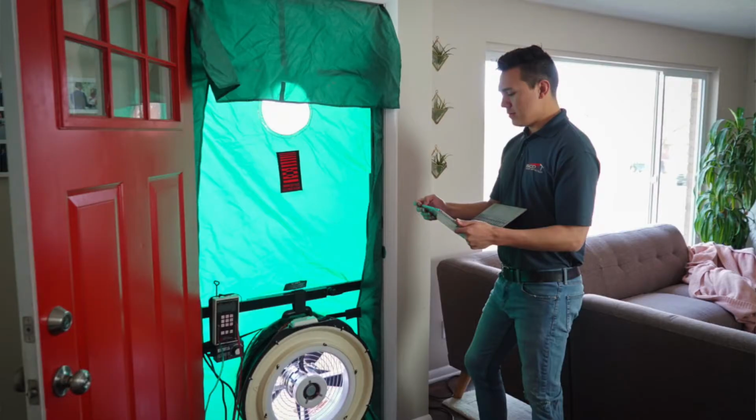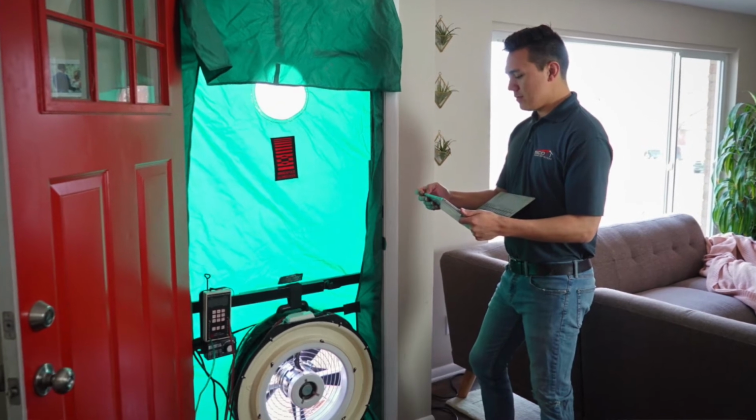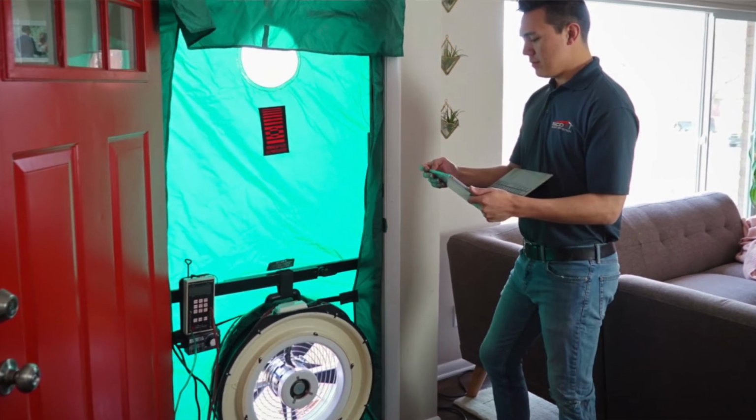So what you're doing with this third retrofit measure is you are electing to make the house tighter than that 7 ACH requirement across all projects, and you're saying, no, we're actually going to shoot for 5. So maybe when you do the energy assessment and you run the blower door test and you find the house is already at 3 or 4 ACH, then you can reasonably assume that post-construction it's going to be at least the same, maybe even better, that you could satisfy that 5 ACH requirement.